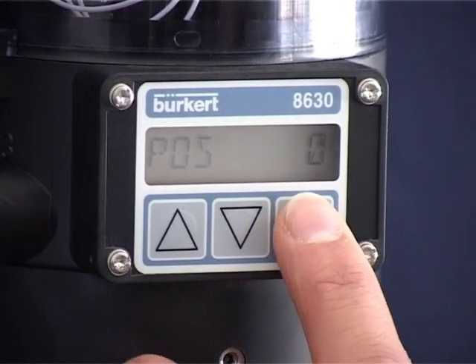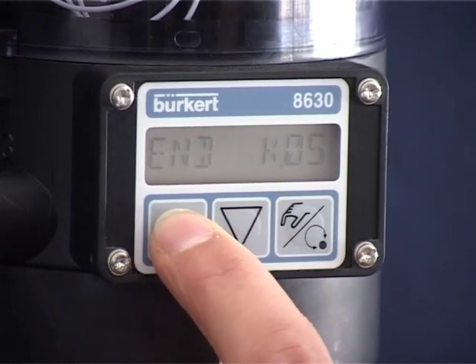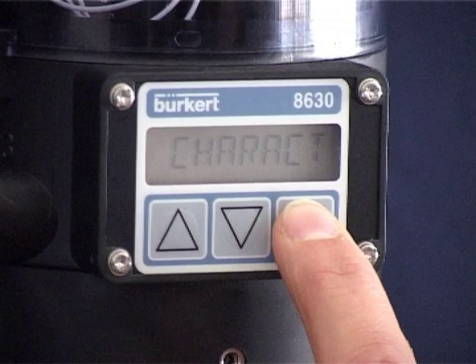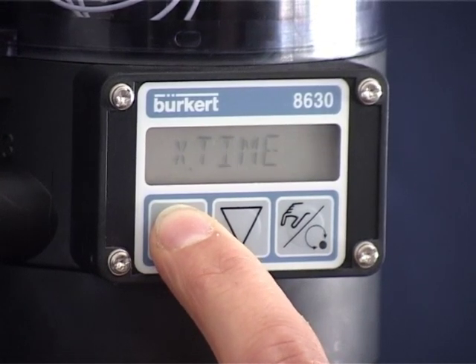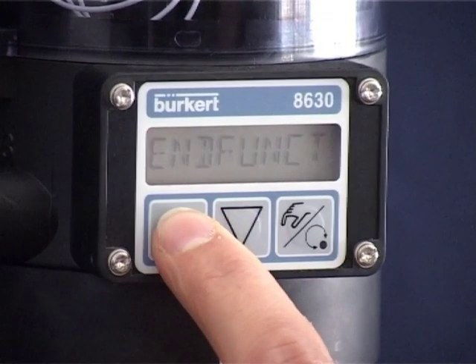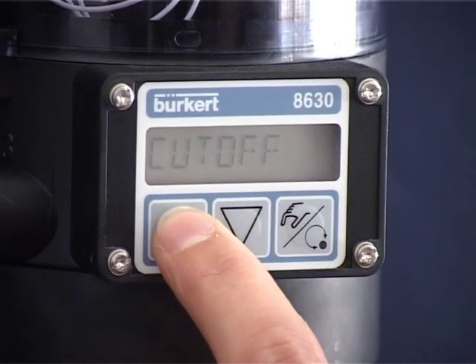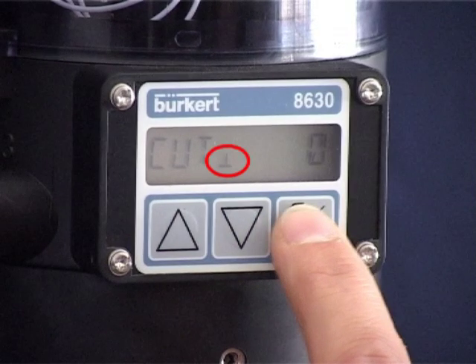Press the right-hand button for five seconds until End Funct appears in the display. Use the arrow keys to select the Add Funct menu item. Confirm the selection with the right-hand button and Charact appears in the display. Use the arrow keys to search for the Edit Cut-off function. The star symbol appears in the display as soon as you confirm the selection with the right-hand button. End Funct appears in the display and you are in the main menu again. Use the arrow keys to select the Cut-off function for the settings, confirm with the right-hand button, and Cut appears in the display.